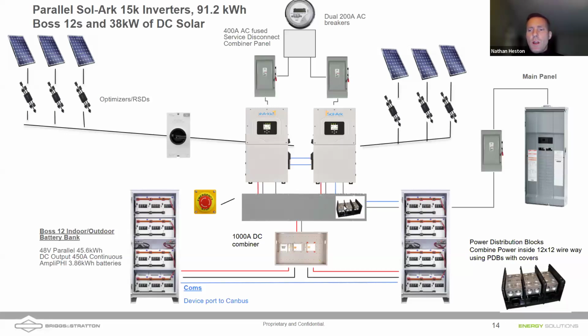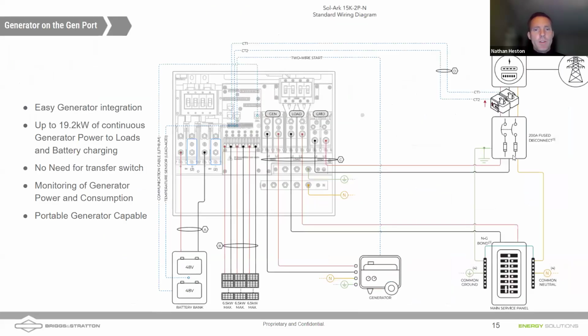You could also use power distribution blocks as a combiner if you've got DC breakers built into your system elsewhere. I'll show a little bit later battery combiners using the Victron 1000 amp combiners, where you have Class T fuses that you can use. Notice that this larger system has 400 amps of pass-through, so each inverter offers 200 amps of pass-through. Got separate breakers there showing separate disconnects, 200 amps each, feeding each of these. And then that overall load center of the house could be up to 400 amps. So a separate option there.